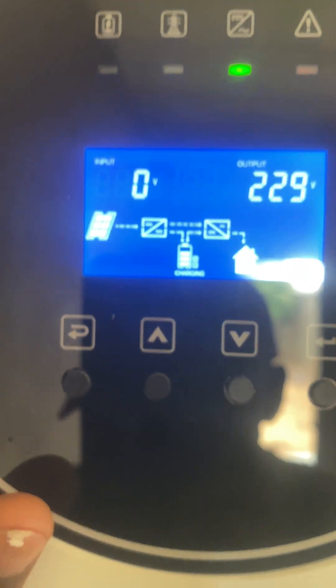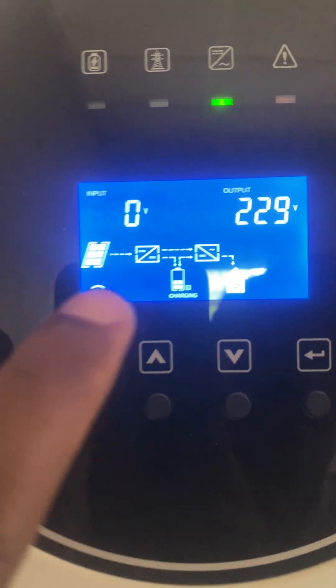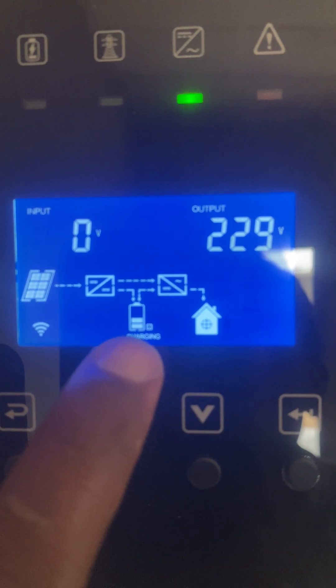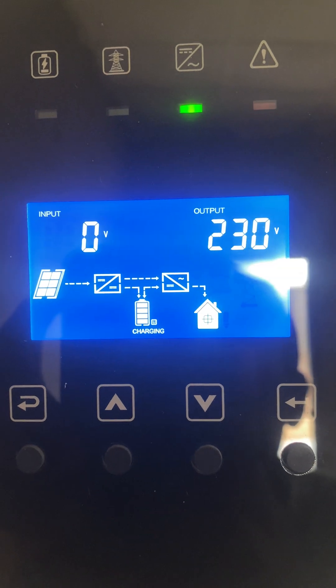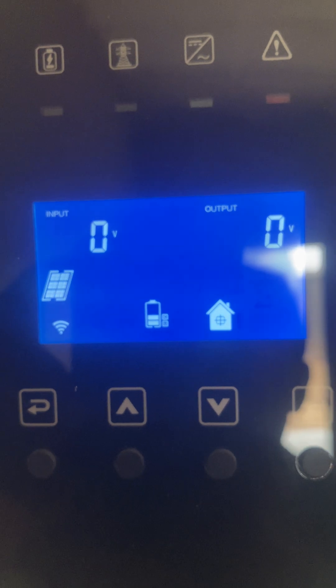Keep in mind that any time you turn this machine on, it will show zero communication for a moment, then the error will start if it's set to lithium and not communicating. Let's see what happens when you remove the communication cable while the inverter is on lithium — you can see Error 80 appears. Let's put it back: after a moment it detects the communication again and the lithium setting is confirmed. Thanks for watching.